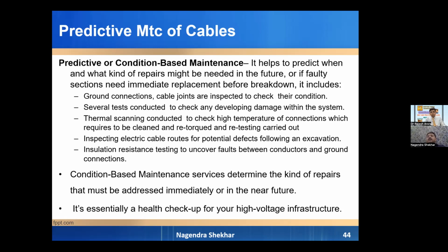If the length of cable is 4 to 5 kilometers and leakage current is very high, we inspect and divide the cable into 2 portions by cutting it at any joint, so that we can find which cable portion is faulty. In such conditions, we even need to replace previously made joints. So joints can be replaced, or we have to find out the reasons from where the current leakage is occurring.